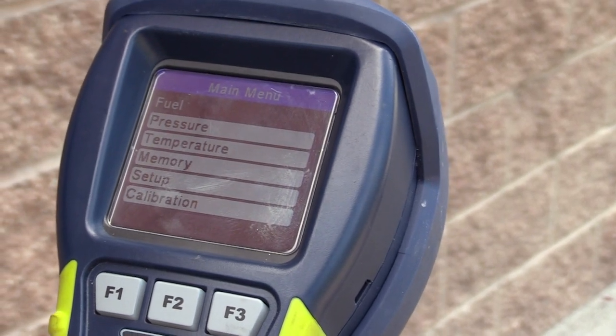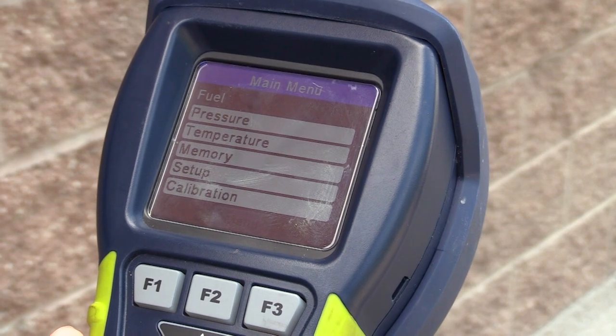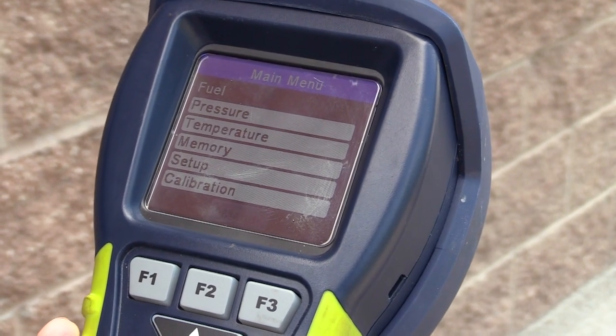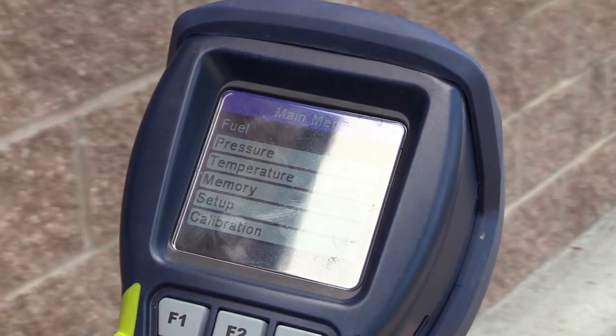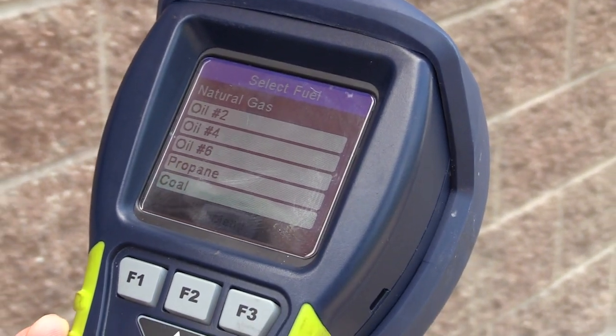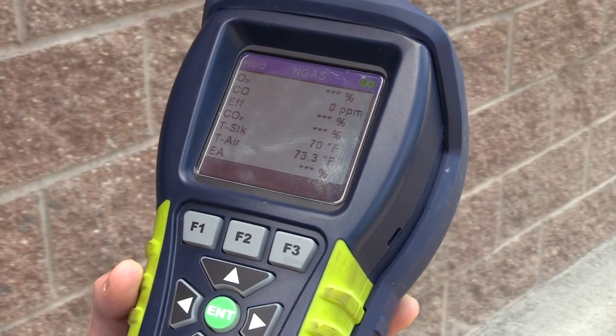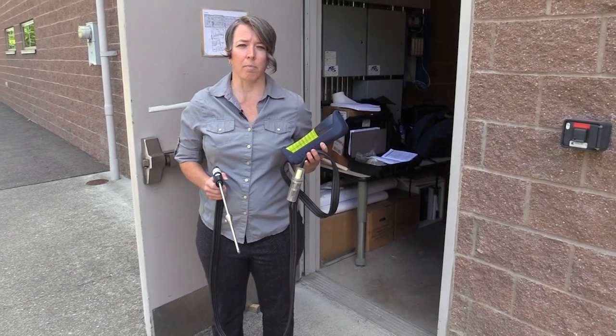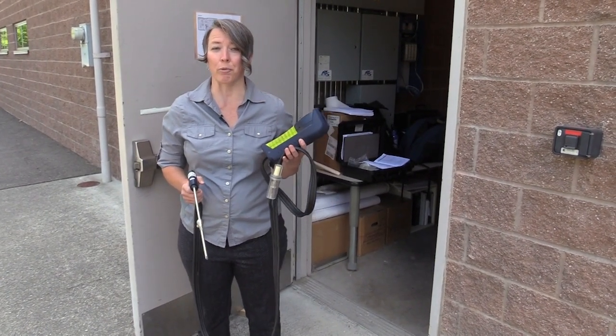I'm going to go into the main menu. There are default settings that should be fine for most applications, but I do want to make sure that I set the fuel. I've got the fuel selected, I'll press enter — this is a natural gas boiler so I'll make sure it's set to natural gas. Now it's ready to take a reading. Everything is set up, so let's head into the boiler room.